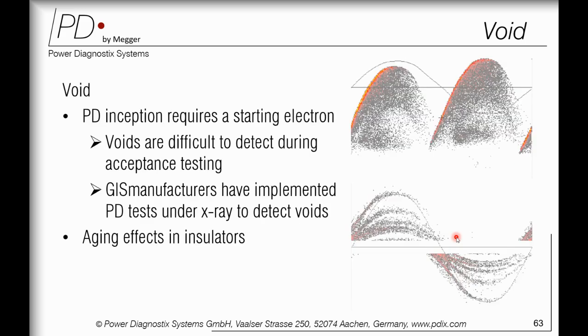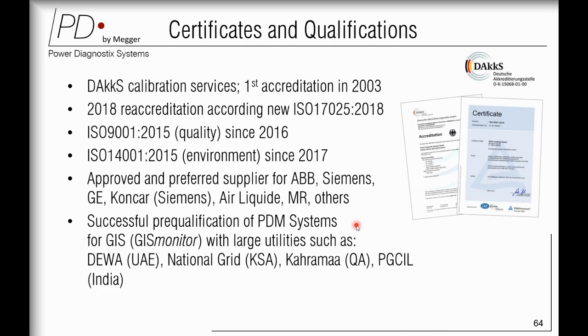You have voids. So these are the multiple void patterns. Voids are difficult to detect during the acceptance test because they might be very small, but over a period of time they will get detected. GIS manufacturers have now implemented X-ray to detect voids, but not everybody is doing it, though some OEMs do that as well. Voids develop over a period of time due to aging effects in your insulator supports. So these were the patterns.